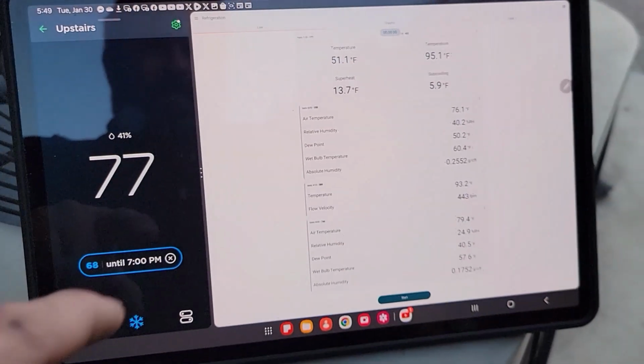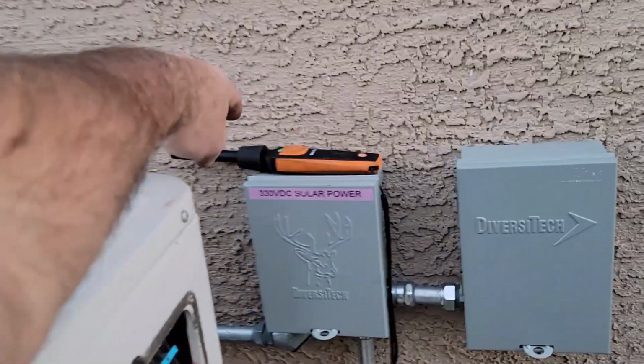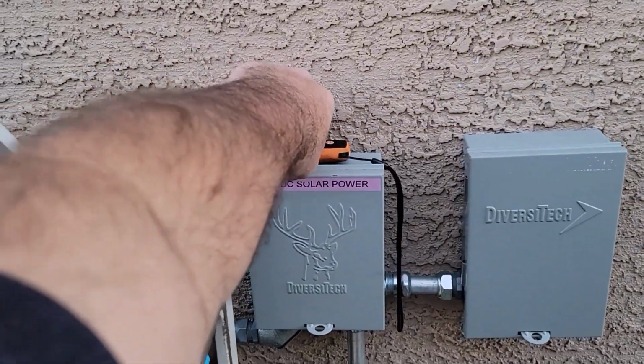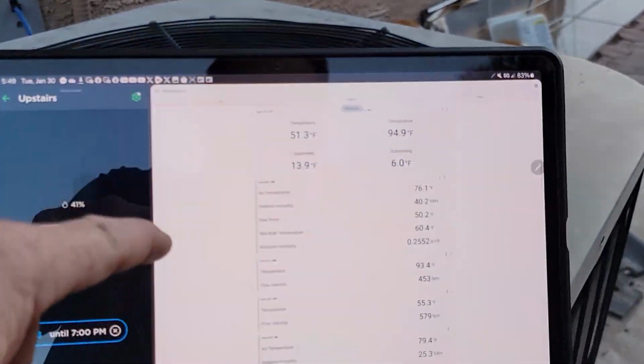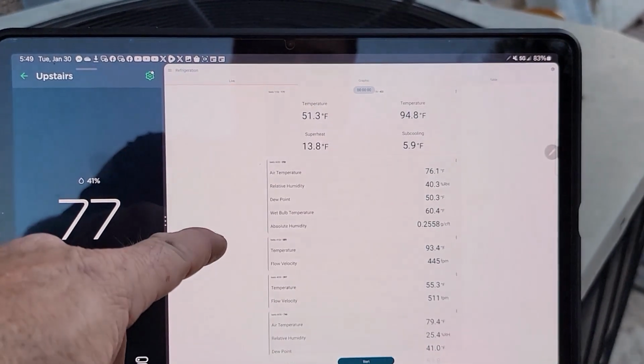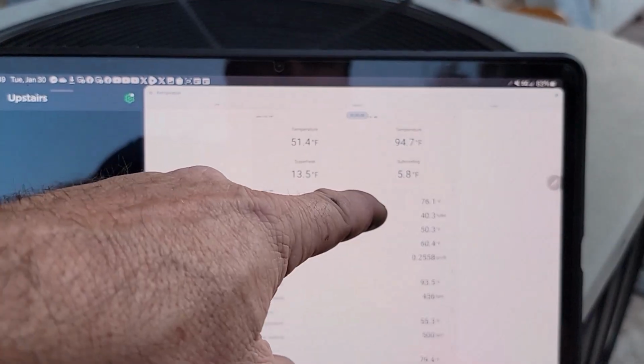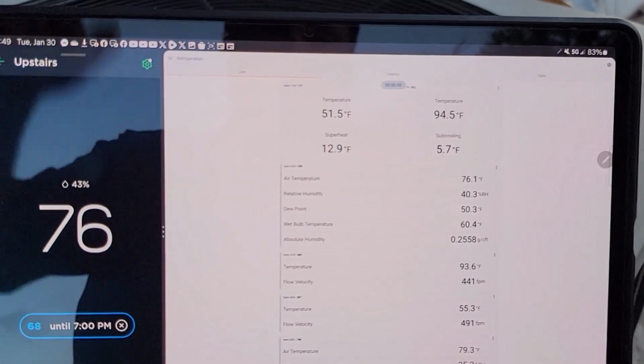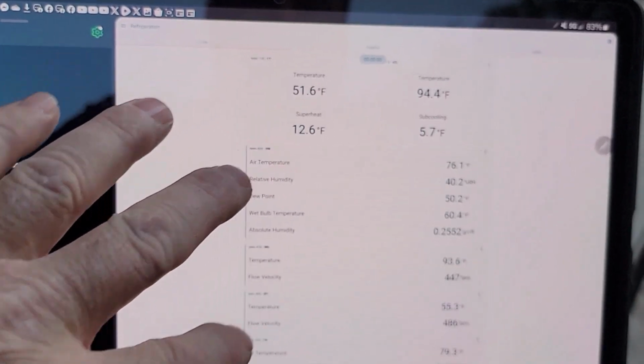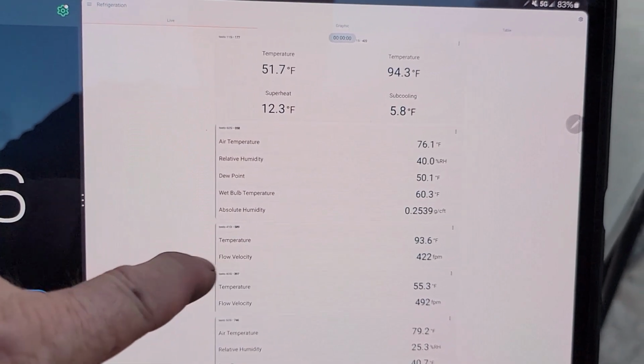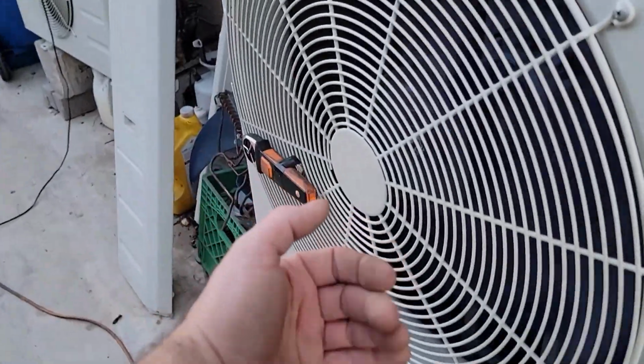Oh man, come on. Is that the outside temperature back here? It's probably recirculating just a little bit or something. I'll put that — 55 coming out the vent, 76 still in the return vent. This is actually shoved in the return vent. So that's an actual 20-21 degree split now, and 93 degrees leaving here.